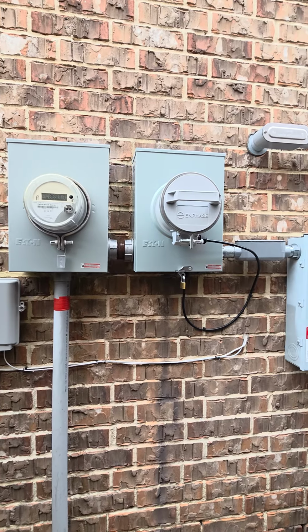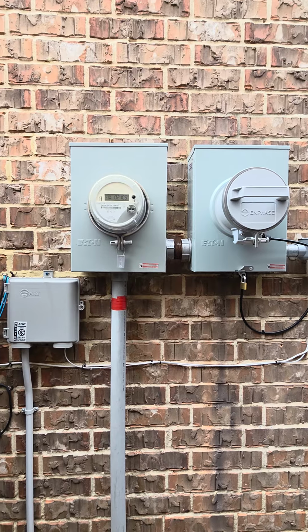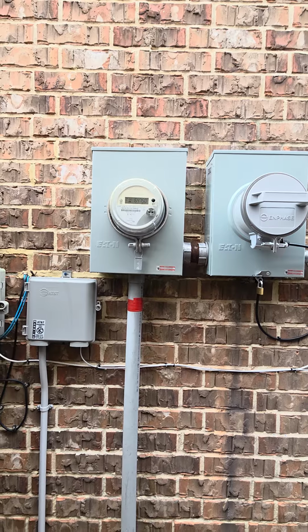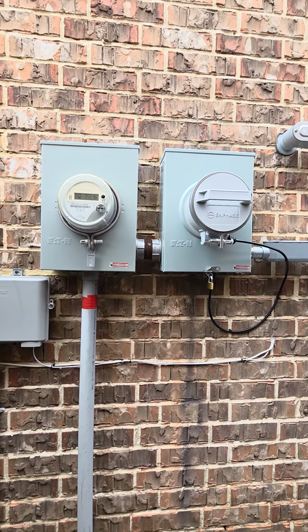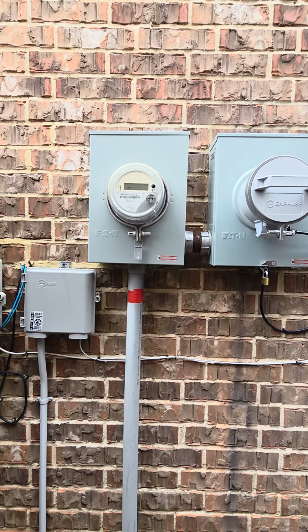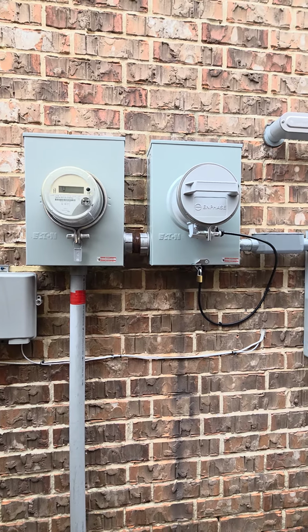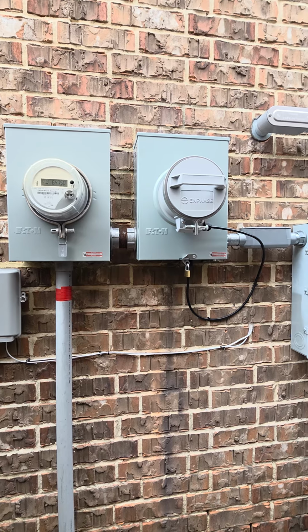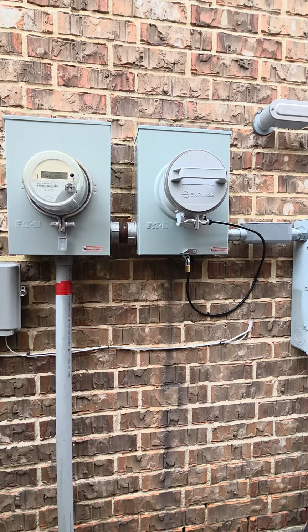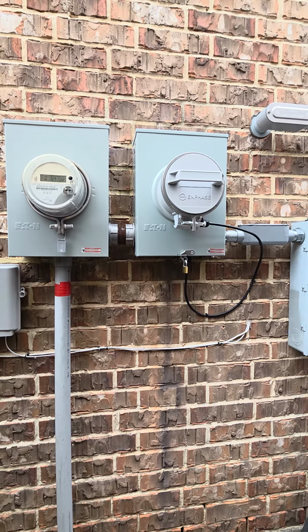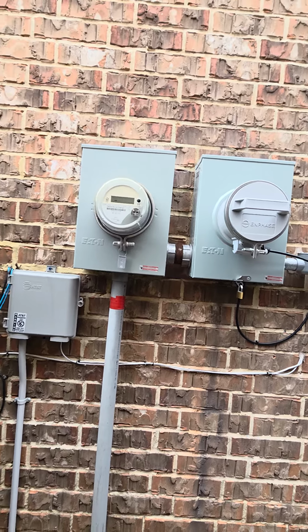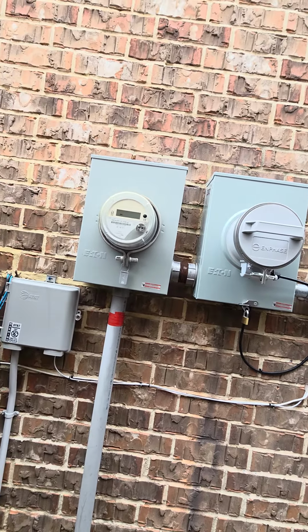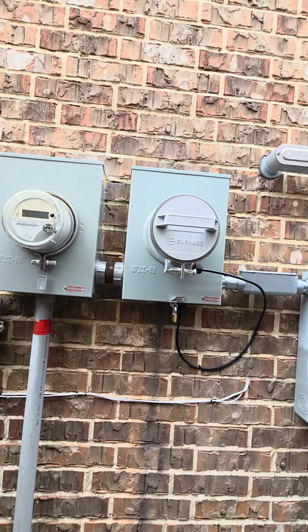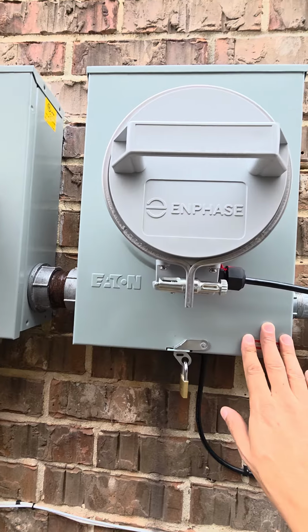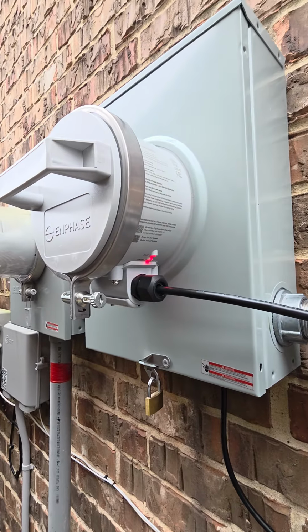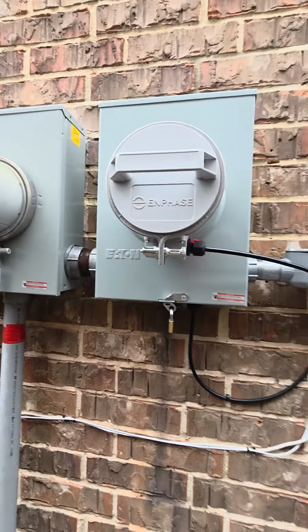As you can tell, I'm using the collar here, and I'm in Houston, Texas. Unfortunately, CenterPoint Energy did not approve the collar for an install over the meter. I even reached out to them and offered to send them the collar if they wanted to do a bench test on it, just to see if we could get it approved. They responded saying they have no desire whatsoever at this time to get it approved. So if your utility does not approve a meter collar installed directly over or under the meter, you need to get another meter socket downstream of your meter and have it installed, and that is where your collar resides.